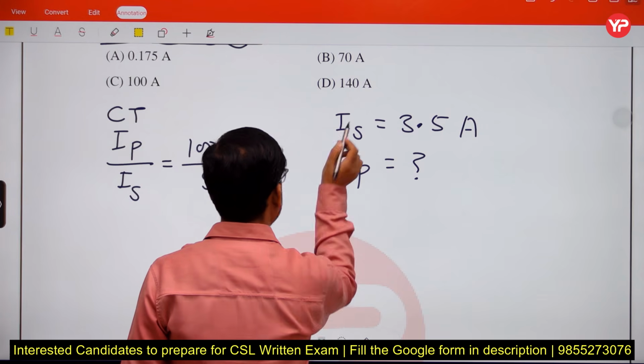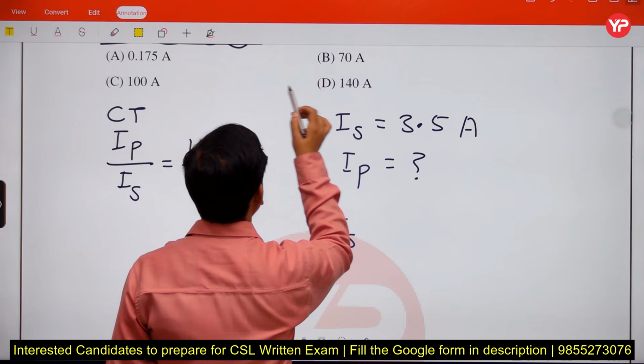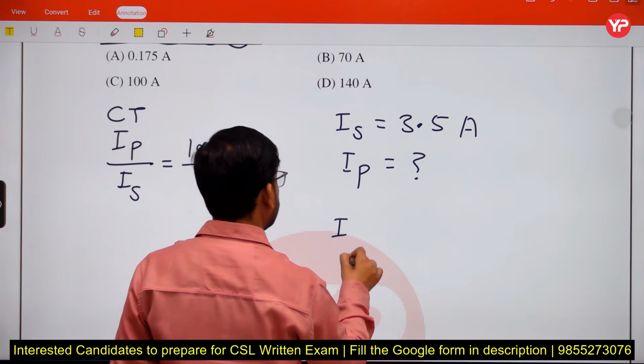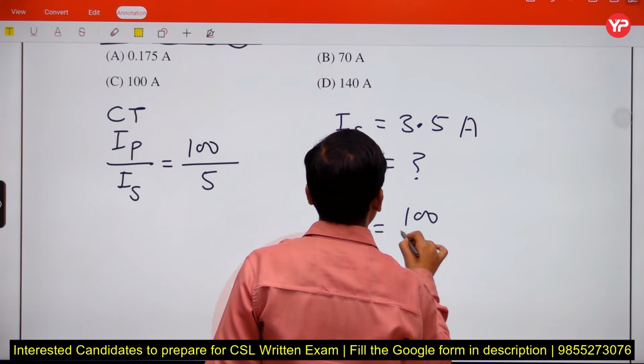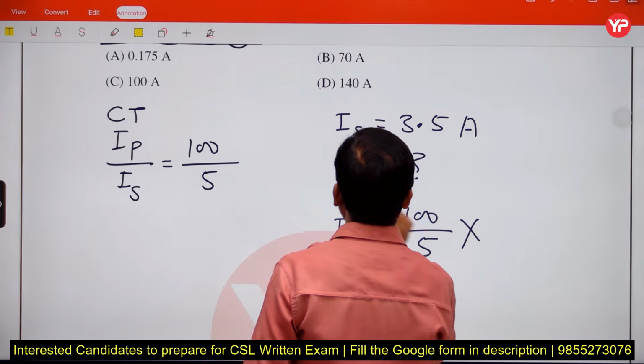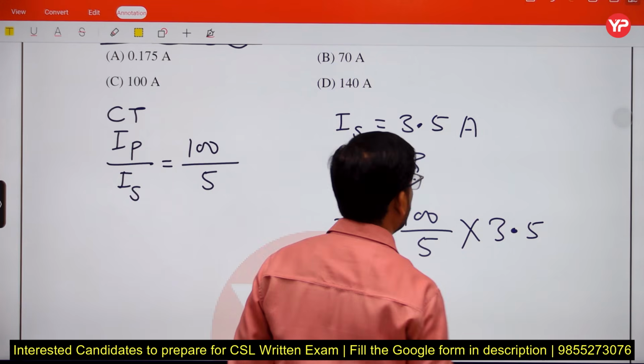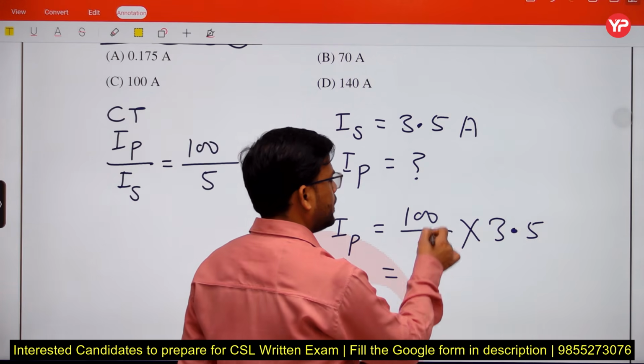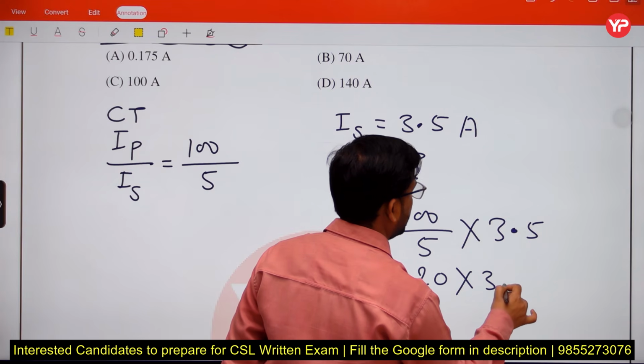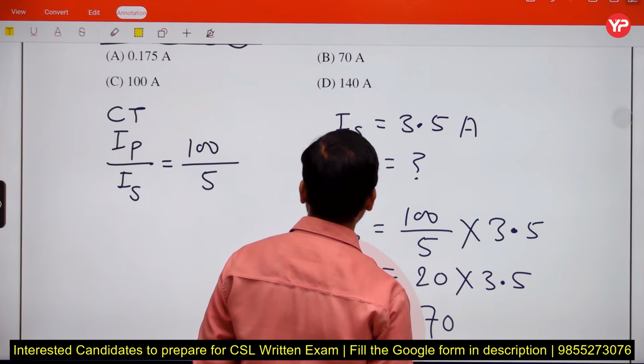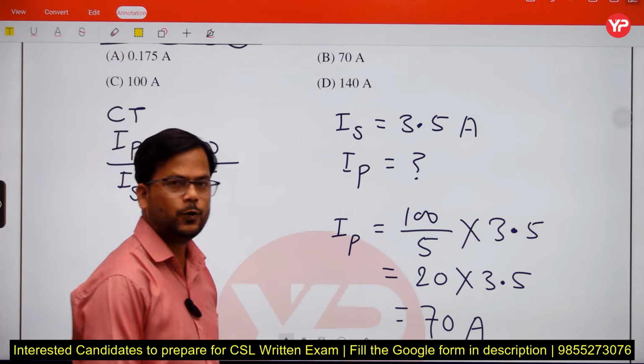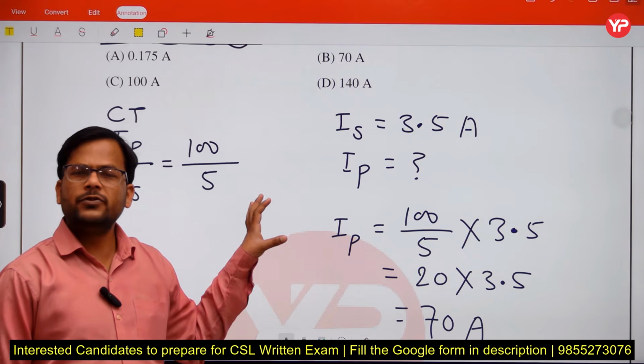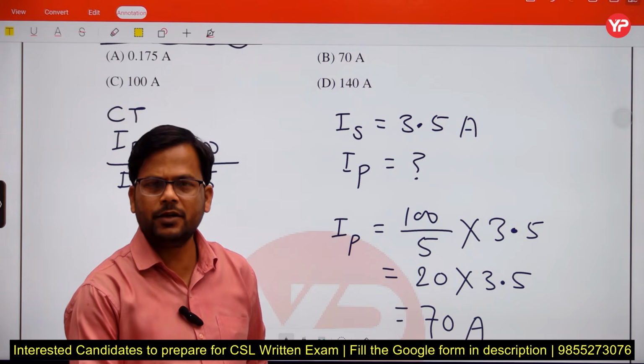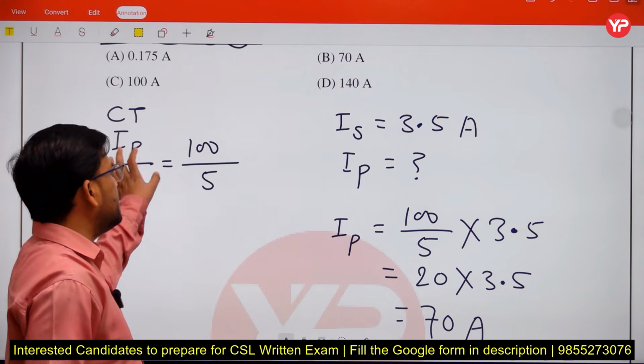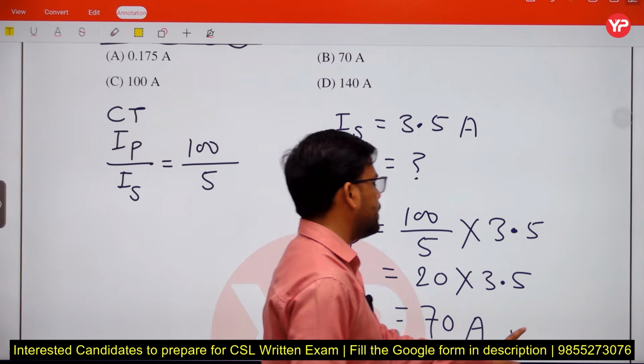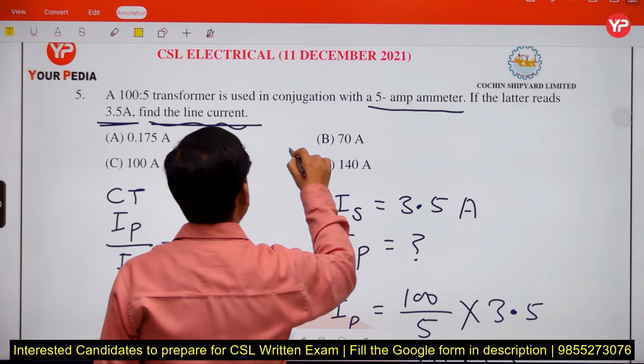Using this ratio, if we put in the value of IS, IP equals 100 upon 5 into IS, and IS is 3.5. If we simplify, 100 divided by 5 is 20, and 20 into 3.5 gives 70 ampere. So for the CT transformer connected with the 5 ampere ammeter, the current on the primary side is 70 ampere. The correct answer is option B.